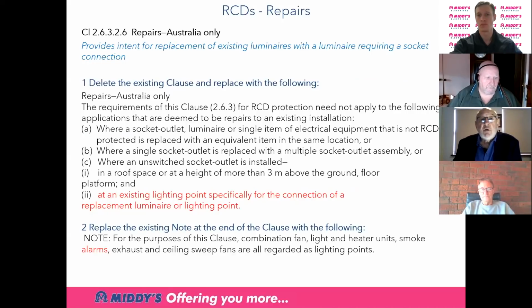And as far as repairs go, we've had to add in a bit to the clause about luminaires or lighting points. So if you have an existing luminaire that may be direct connected, so it could be connected directly to the fixed installation, whenever you replace that, so you're going from a halogen to an LED downlight, for instance, they've now got a plug and socket on them to make it easier for assembly. So at that direct connection, you'd actually have to connect in a plug base, have a socket outlet in the ceiling to connect that. So if you do add a socket outlet, it doesn't mean you have to go back and change the circuit to have an RCD. So that's what the red addition is.